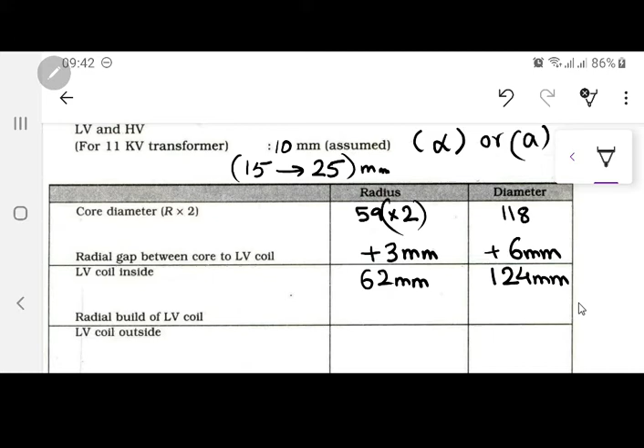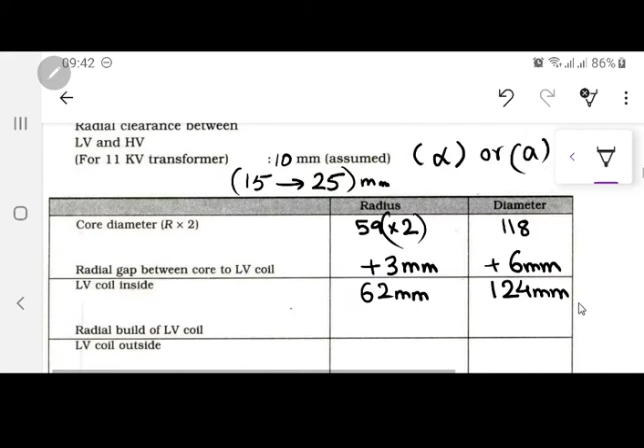Now when you are going to add the low voltage coil, the radial build of the low voltage coil - if we go back over there, the build was 19.1. 19 is a good figure, but since we took 19.1, we should have also approximated it to 19.5 or something, but still we will go with this one, no issues. So this will go with 19.1 mm over here. This is the radial build.